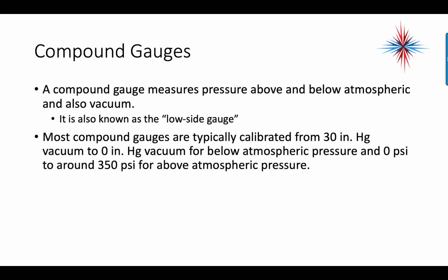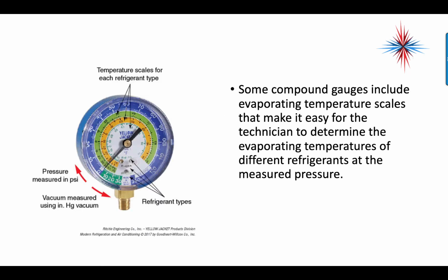A compound gauge measures pressure above and below atmospheric and also vacuum. It's known as a low side gauge. But you cannot use a compound gauge just for drawing vacuum. It does not do microns. Most compound gauges are typically calibrated from 30 inches of mercury vacuum to 0 inches of mercury vacuum for below atmospheric pressure, and 0 psi to around 350 psi for above atmospheric pressure. Some compound gauges include evaporating temperature scales that make it easy for the technician to determine the evaporating temperatures of different refrigerants at the measured pressure.